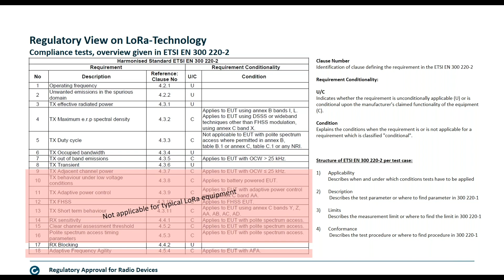So in the end, we have those 9 tests. Operating frequency, of course, we want to make sure that the device transmits at 868 and not at 915 in the European Union. It would be the other way around for US testing, but during this presentation, we're concentrating on testing for the European Union. Unwanted emissions in the spurious domain means it really only transmits at 868 megahertz and does not have side lobes, side interferences. TX effective radiated power: you may know that short-range devices in that frequency band are allowed to emit at 14 dBm, which means 25 milliwatts at a max.